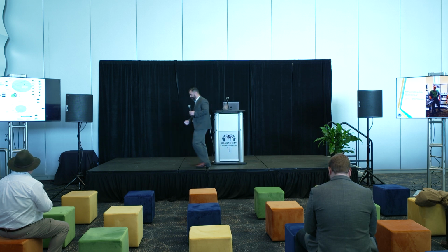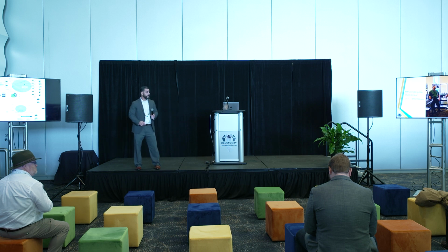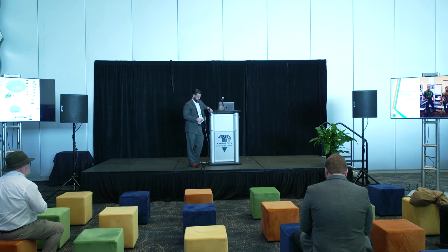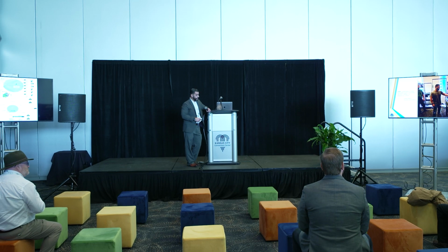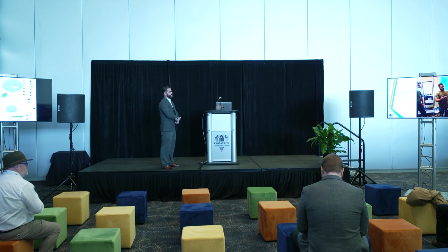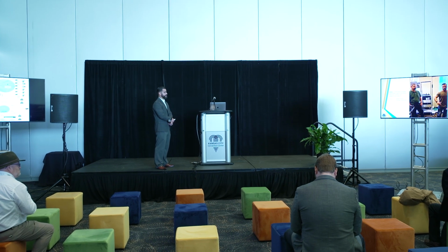That's good. All remote spokes have access to both hub 1 and hub 2, and the polling devices behind them. And so we're going to perform a test where we're going to simulate a failure a couple of ways on hub 1 and show that traffic is still traversing hub 2's link out to all the remote spokes. So for this example, if you look here, Joe, we're going to use remote spokes 1, 3, and 5, which have SEL devices on the LAN side. And I'll let Clayton explain which devices we have at the hub 1 and 2 routers and the 3 LAN devices for the test as well. And then we'll go ahead and commence the test.